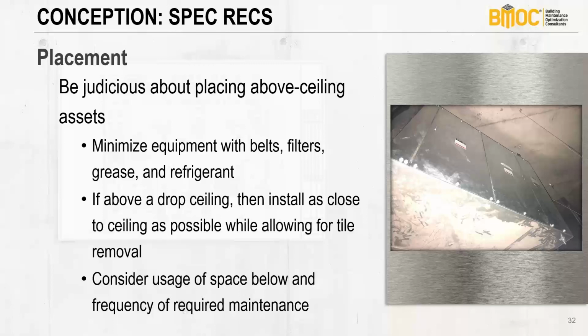So you can't work on this unit from a ladder. Everything's too heavy - those nuts are about 1/2 inch - and you need heavy equipment to take them off. There's a belt in there that you have to service quarterly, and you also have to remove part of the ceiling grid structure to get to it. This one was tough to service.